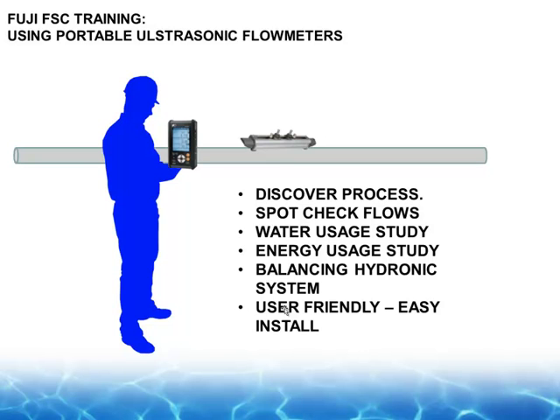You're going to use a portable device you're going to strap on nearby, and so flow survey people do that, or the maintenance people can do that themselves. So you can do water studies, you can do energy studies. Temperature, BTU calculation studies are hot potatoes right now. So you can monitor flow along with temperature.